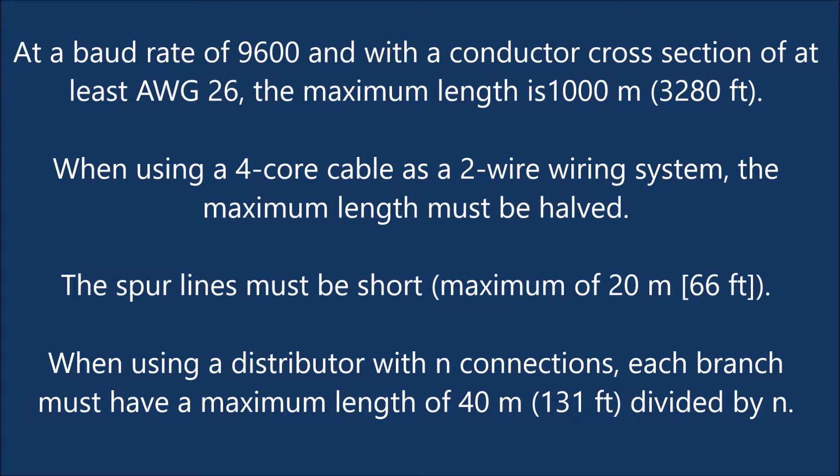At a baud rate of 9,600 and with a conductor cross-section of at least AWG-26, the maximum length is 1,000 meters (3,280 feet). When using a 4-core cable as a 2-wire wiring system, the maximum length must be halved. Spur lines must be short — a maximum of 20 meters (66 feet). When using a distributor with N connections, each branch must have a maximum length of 40 meters (131 feet) divided by N.